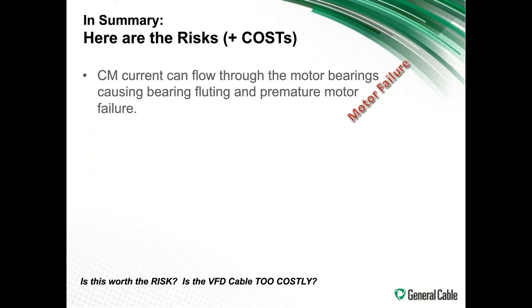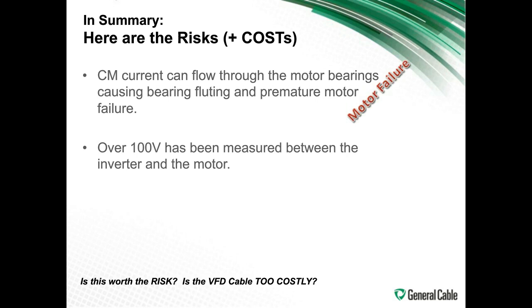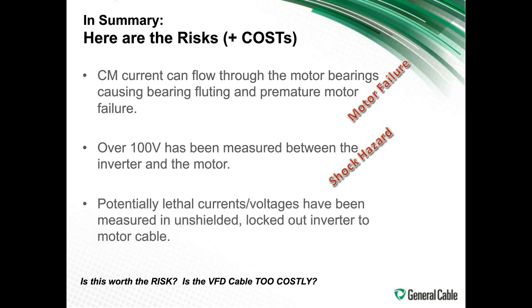So here are the risks and costs, in summary, of common mode current. Causing motor failure, because it flows through the motor bearings and causes the fluting and premature motor failure. We have 100 volts that can be measured between the inverter and the motor that can cause a shock hazard. Don't want to see that. And then we also have the other risk of lethal currents that leak through, and you basically go in an unshielded, locked out inverter to motor cable. That can actually cause a life or death situation. If you look at all this, can you afford this risk? Is the VFD cable too costly now?